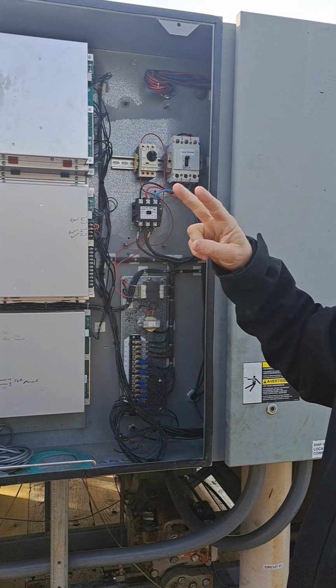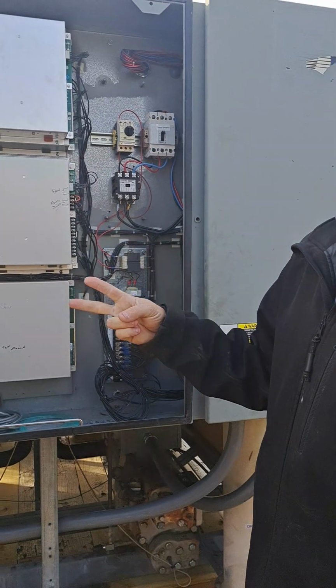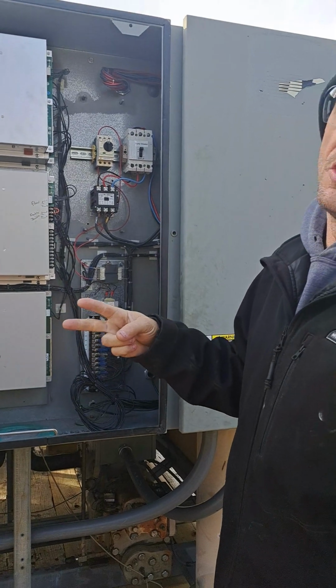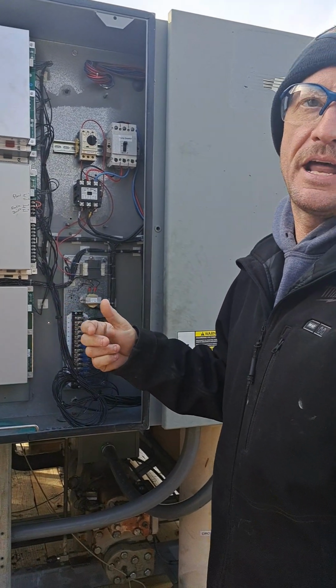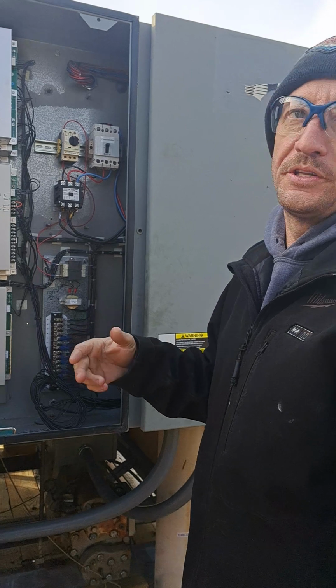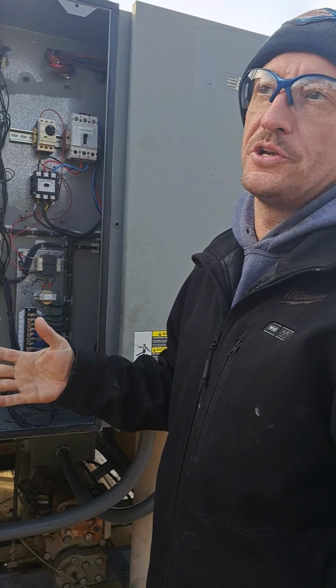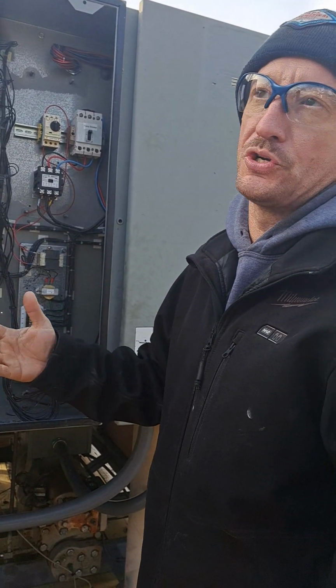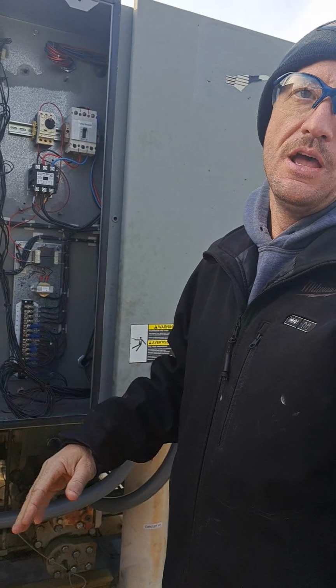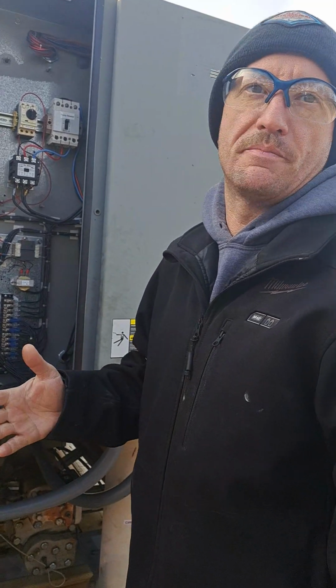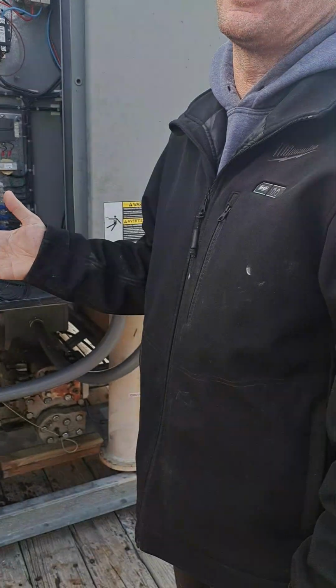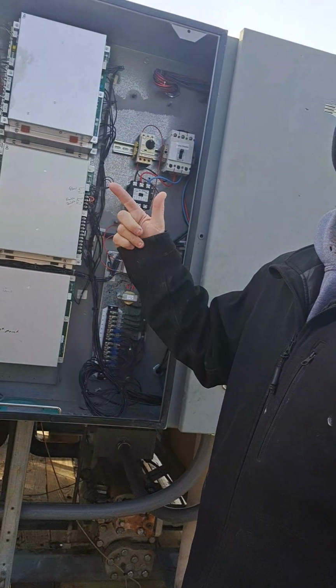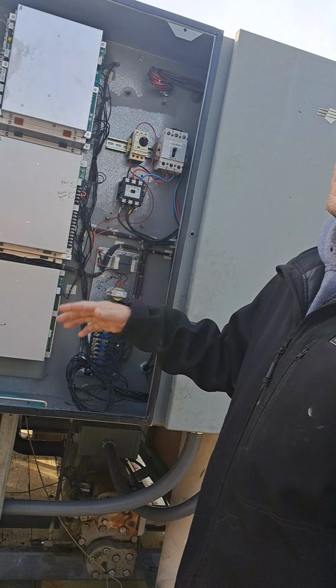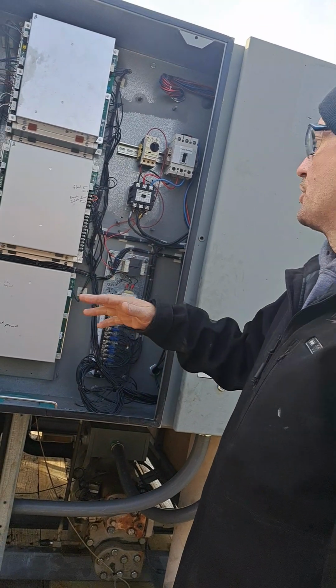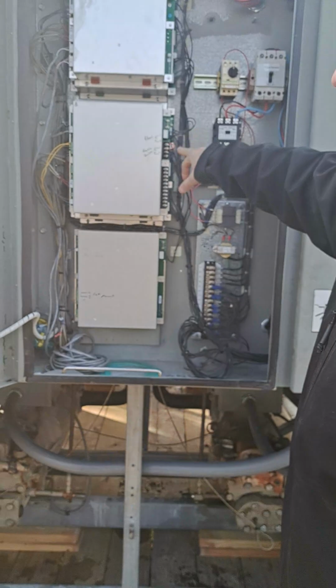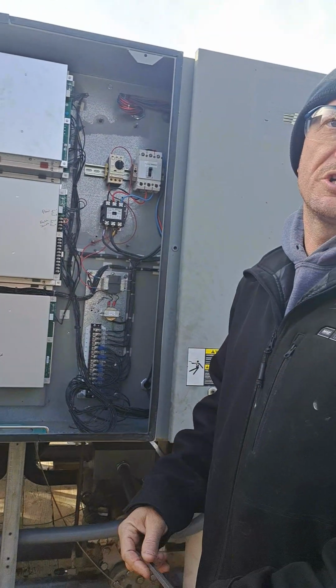This chiller does not have any flow proving on it now, so there's no flow switch. So it might be a good idea to maybe add that in the future, because you don't want this thing starting up with no flow, because you can freeze the chiller barrel up, burst tubes, all that kind of stuff. The flow switch is a basic safety item that's on every piece of equipment that's liquid cooled. Generally, it's installed in the piping system after a piece of equipment's put in place. So that's what these jumpers are right here, and I've jumped out the flow switch because you don't have one.